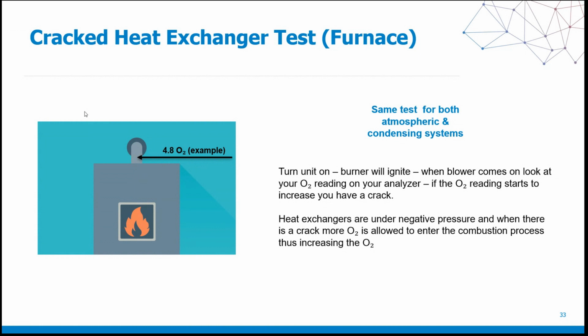So you're introducing more oxygen that's not supposed to be there. And by doing so, your oxygen level is starting to rise as that fan and that system continues to run. So whether it's 5.6, whether it's 12.4, either way, you have a crack. And the last time I checked, cracks don't get smaller with age. They get bigger with age.